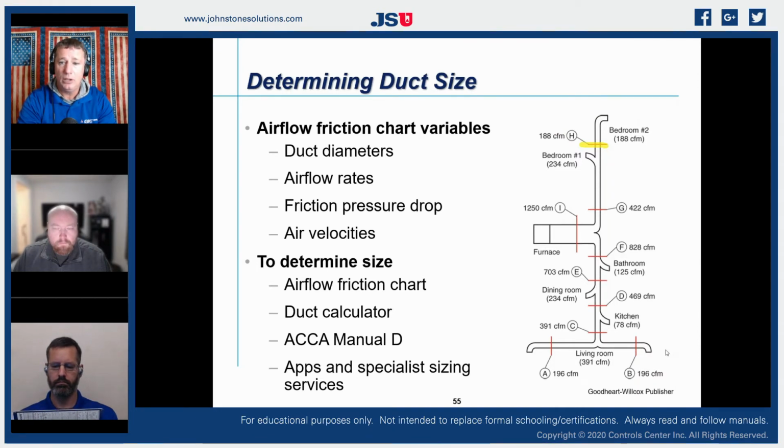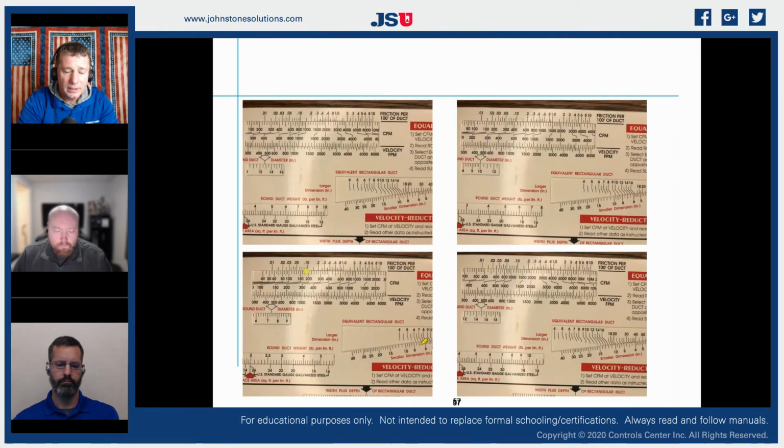So if I look at 188 CFM at 0.1, if I'm running an 8-inch, because I'm running an 8-inch trunk, look there, I'm already down to an 8 by, that says 6. I could have branched that all the way down to an 8x8, because 8x8 would be the smallest transitional that I had in stock.